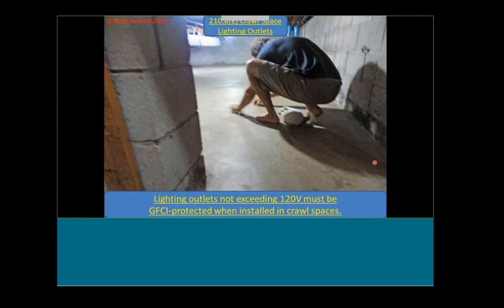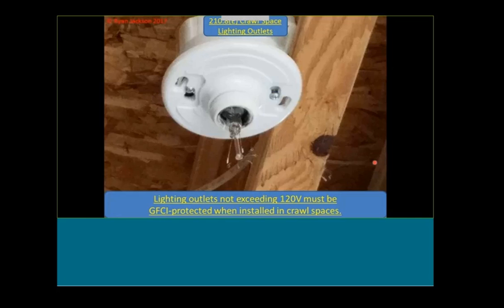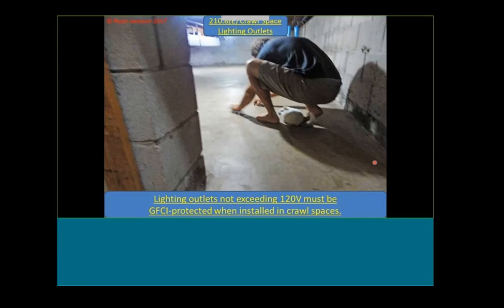Here's what we're concerned about: he's crawling through there, runs into one of these lamp holders, and breaks the light with his back. That thing is still on. It's still energized, still 120 volts. And if you get shocked by that in a situation like this, well, according to the substantiation for this change, the death rate is higher than the injury rate.